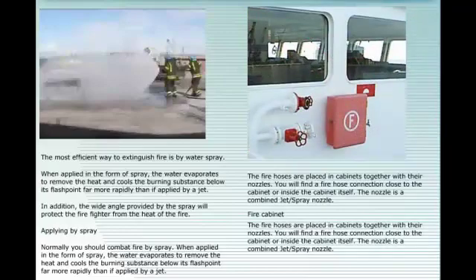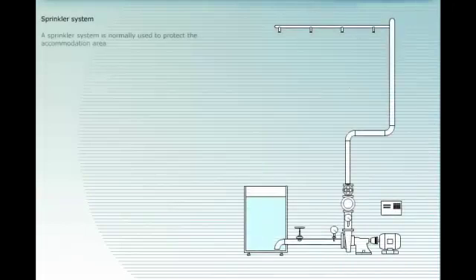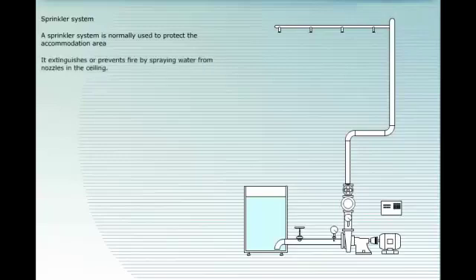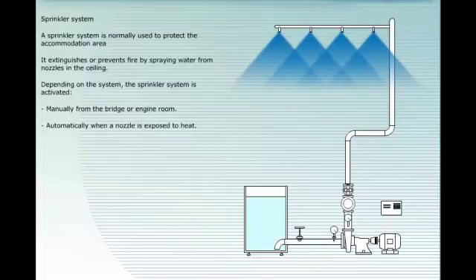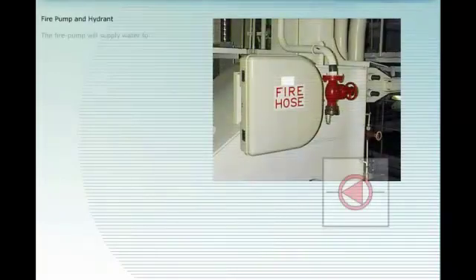A sprinkler system is normally used to protect the accommodation area. It extinguishes or prevents fire by spraying water from nozzles in the ceiling. Depending on the system, the sprinkler system is activated manually from the bridge or engine room, or automatically when a nozzle is exposed to heat. The fire pump will supply water to the fire hoses via the hydrants, the sprinkler system, and the foam system. The fire pump is started from the bridge or the engine room.